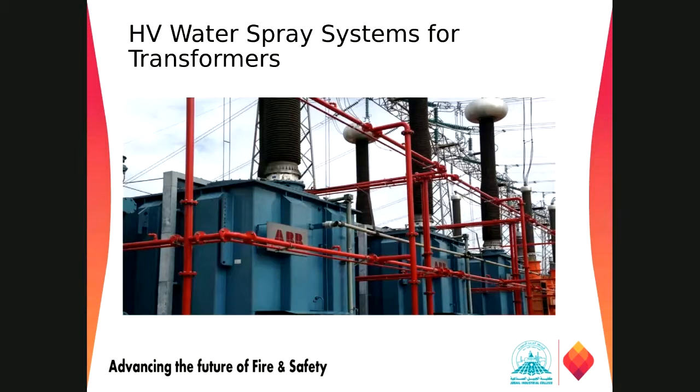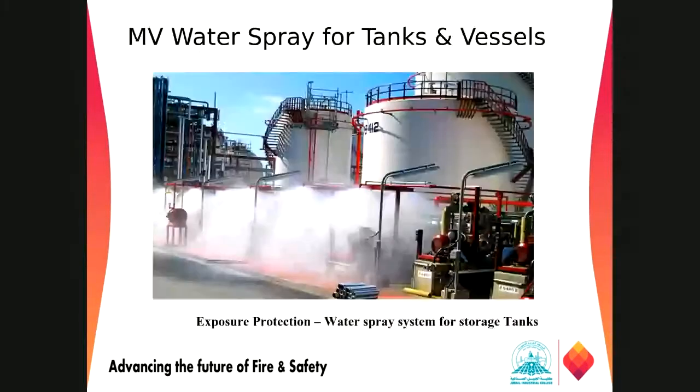If you can see in this figure, we just want water to go onto the surface, not to the outward side. We only want to discharge water onto the metal part. So we need a directional nozzle, which covers only some direction, maybe 120 degrees or 180 degrees. Based on that, we have to space our nozzles so that no area on the surface will go without water in any case.